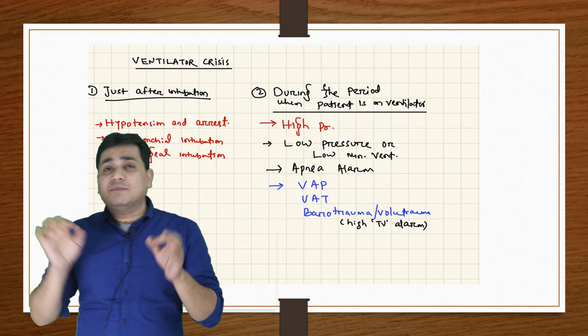Now, what are the minimum alarms that need to be set in the patient in different modes of ventilation? If the patient is in a volume control mode of ventilation, the minimum alarm to be set is the pressure alarm. It is common sense, because in volume control ventilation the volume is constant, so the alarm that you need is the pressure alarm. Similarly, in pressure control ventilation, because the pressure is constant, the alarm that we will need is the volume alarm.